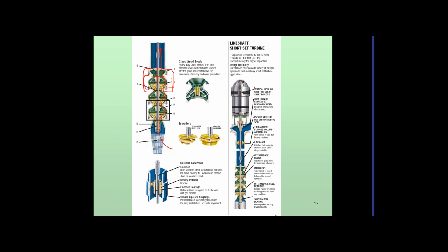On the right here, we've got a picture of the motor with a shaft running down to the bowls. This shaft will have some supports or bearings to hold it. They're either water lubricated or oil lubricated, depending on the manufacturer. So that's how they work. They're going to have a number of different kinds of impellers on these.